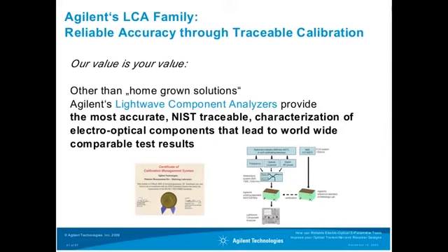Well, in principle, this is true, but it's very important that you have traceable and reliable accuracy, and this is basically that in our calibration, we trace everything back to absolute standards, which we use from NIST, the National Institute of Standards of the US, and we have these absolute traceable standards to which we relate our calibrations and our specifications.